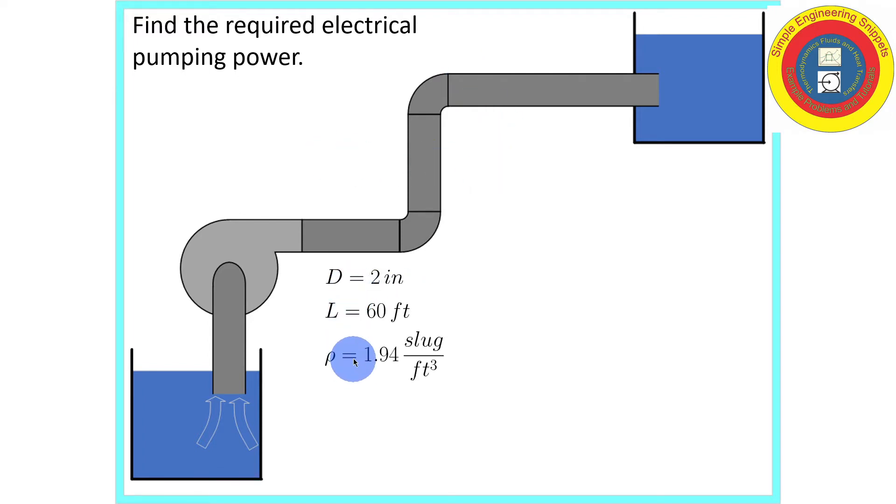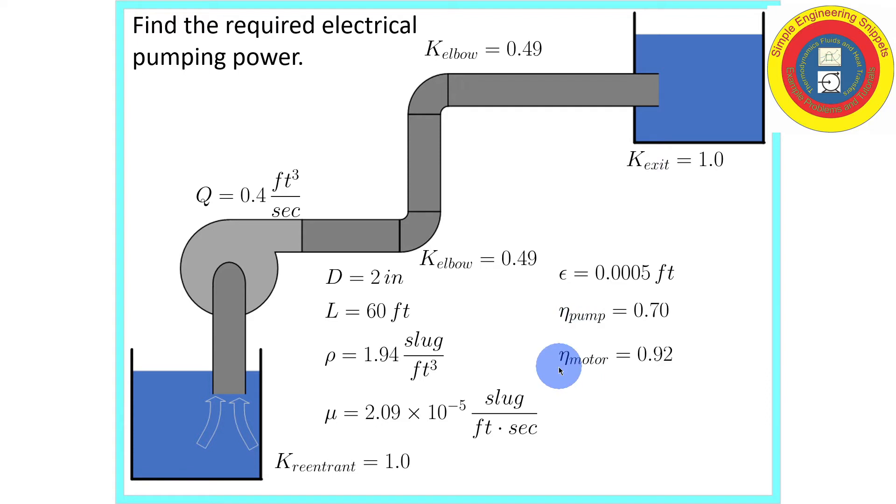Diameter, length, the fluid is water, so we have the density and the dynamic viscosity. Entrance loss is 1.0, exit loss is 1.0, and each elbow has a minor loss coefficient of 0.49. Flow rate of concern is 0.4 cubic feet per second, and roughness of the pipe is 0.0005 feet. Efficiency of the pump is 0.7, and the efficiency of the motor is 0.92.